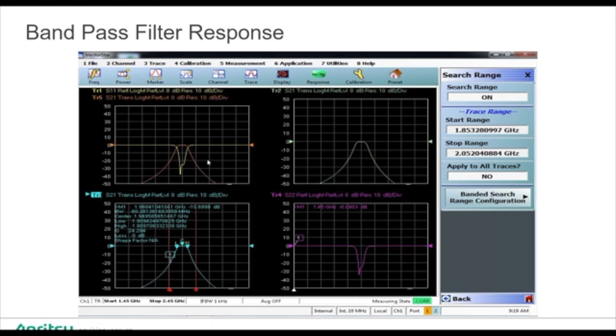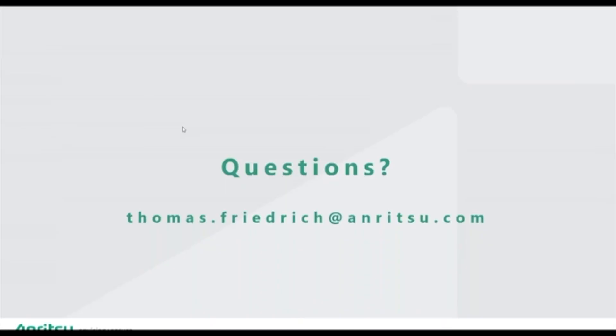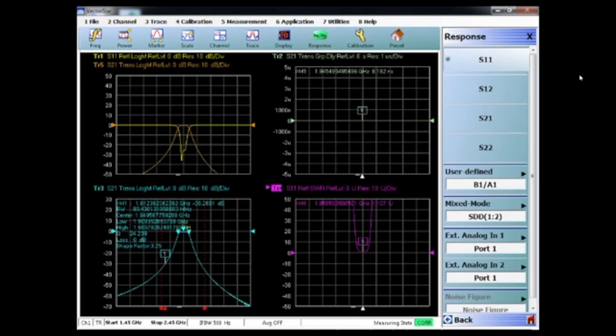Next question: Do all Anritsu VNAs have the Q bandwidth measurement capability, and is it an option or standard? They all do. All of the benchtop models will have the shape factor, Q factor, those types of statistics as well. And I'll bring up a VNA display here in a second. Those are standard. They're not an option, so they're in every benchtop model that Anritsu has.